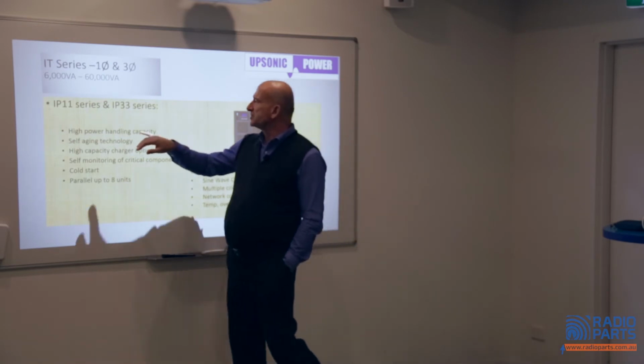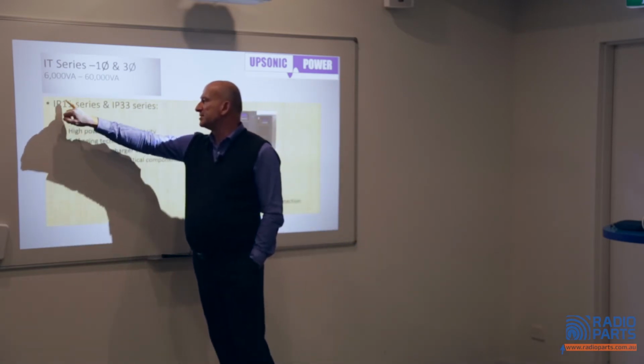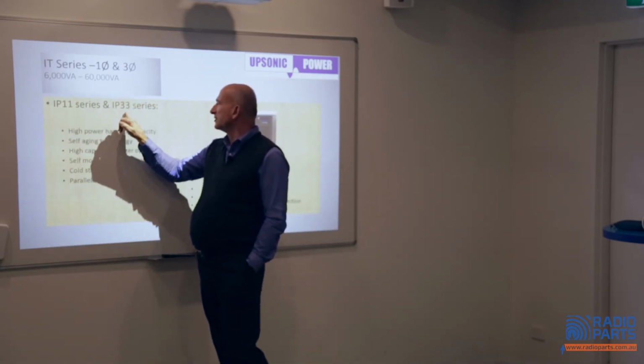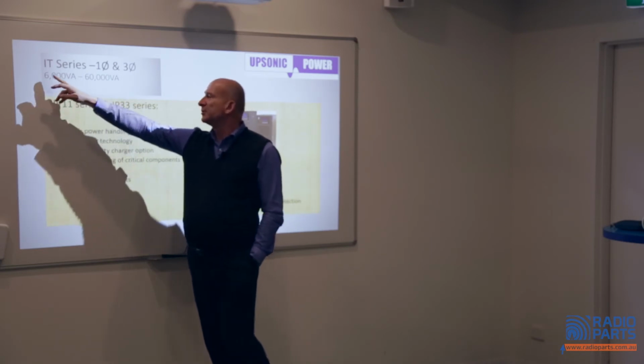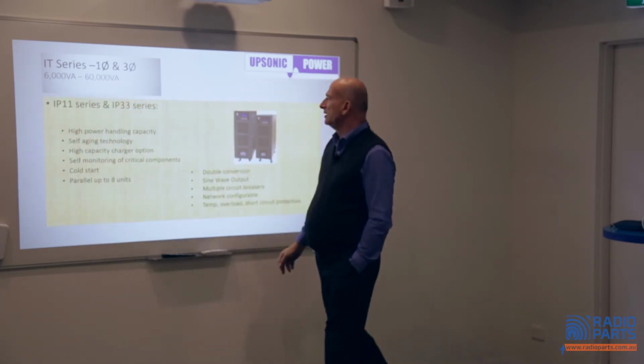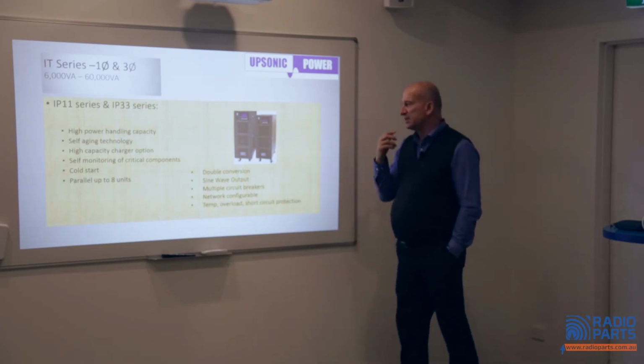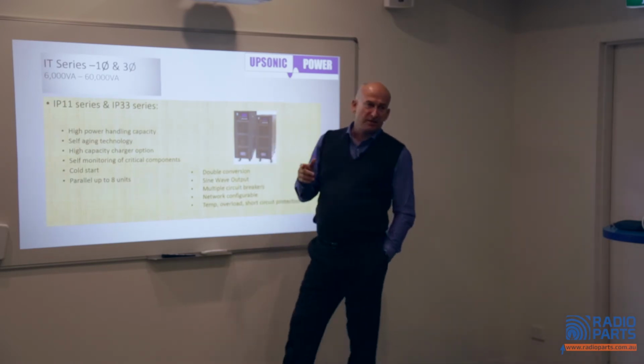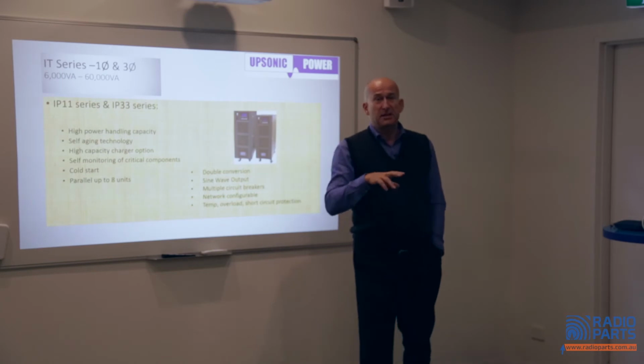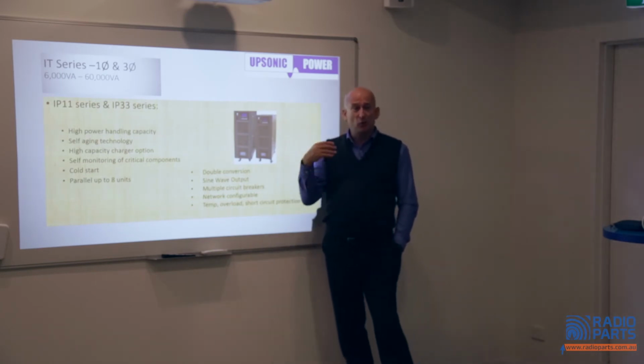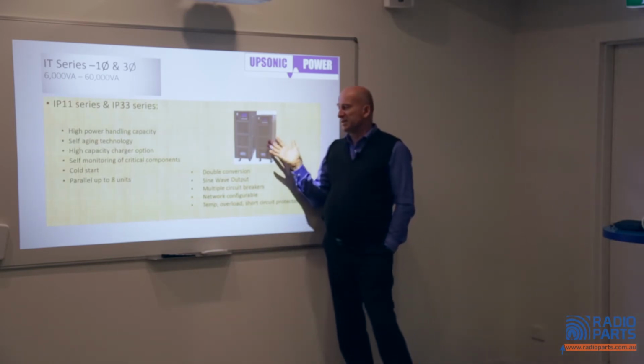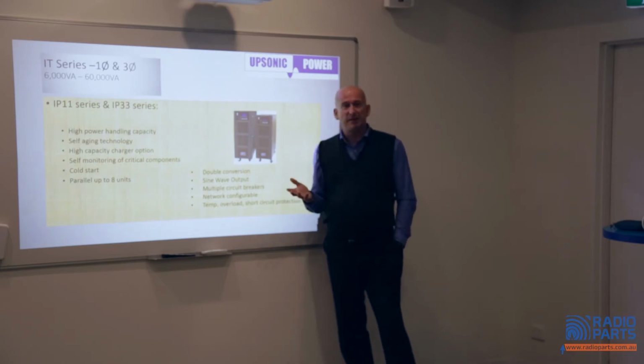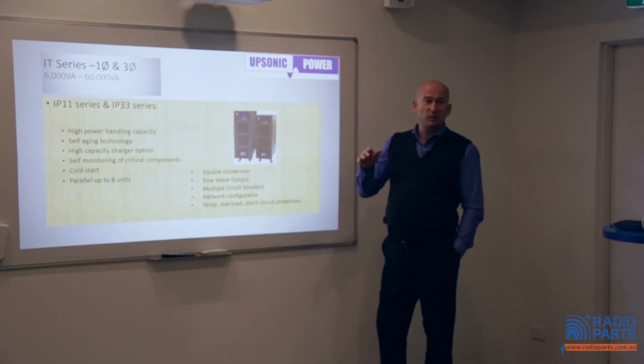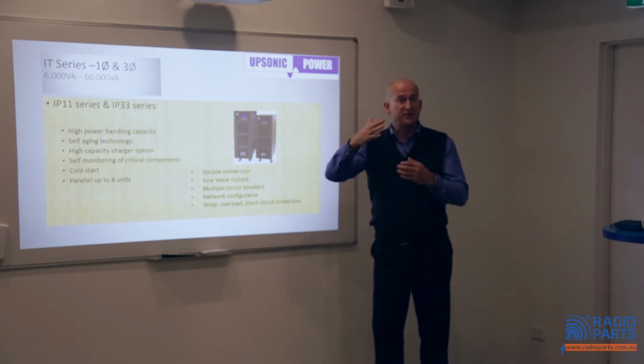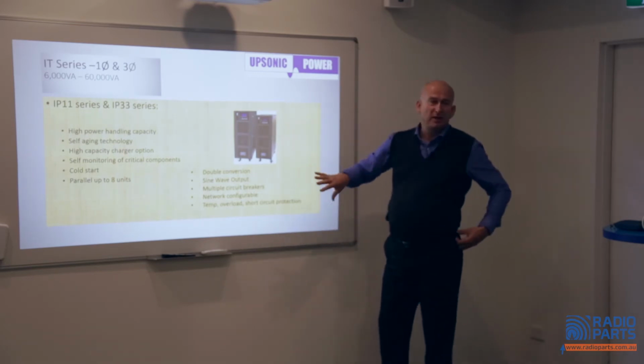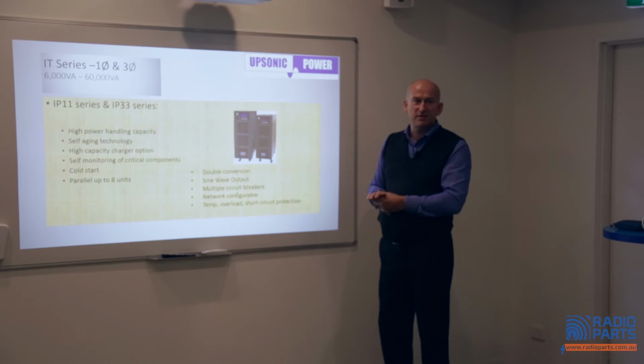This is our industrial series. This is phases in, phases out. So 3 phase in, 3 out, single in, single out. From 6 kVA to 60 kVA. Very high handling capacity. These have self-aging technologies where they'll look at the batteries and see how they're performing and report back. So generally these units need to be serviced on a yearly basis. We come in and look at that aging and we can project how long the batteries will last. So we're getting into critical applications where they have to have these things online.